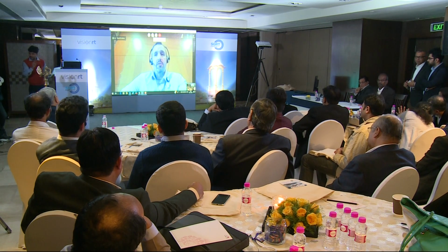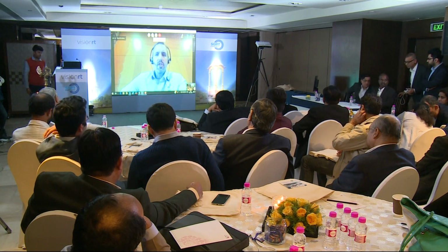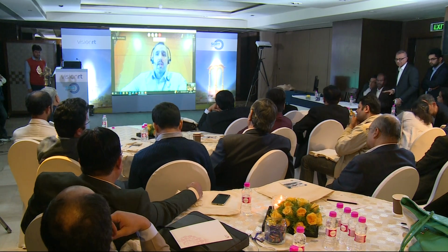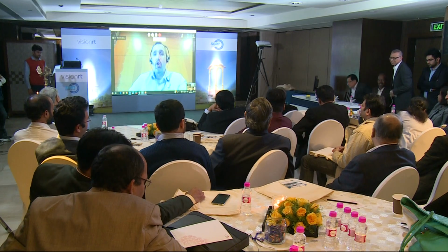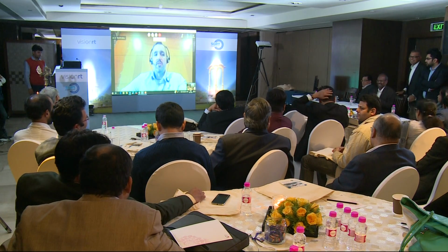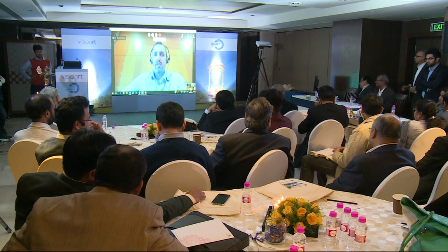I think the ORFIT AIO solution, of all the ones I've used between Civco, Bionix, Q-Fix and all of that, I find that the ORFIT one is the most complementary to surface guidance, because the arrangement of the masks along the surface of the patient always allows you to give an open area that you can monitor with SGRT. And so it's really important for the physics team to evaluate not just, I'm bringing in an SGRT system, but how is that SGRT system affected by my immobilization, by my treatment machine. Obviously, if you have a tomotherapy, it's a very challenging geometry for SGRT because you're basically occluding the patient while they're in the bore.